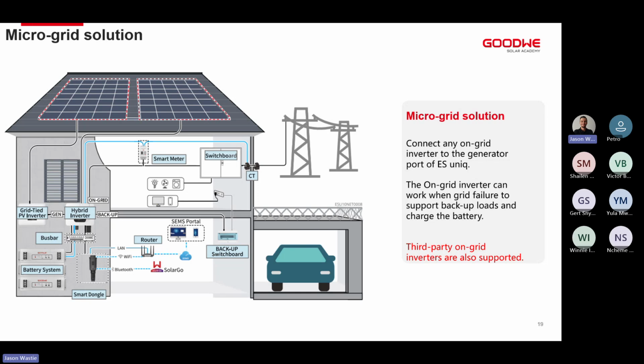One caveat to that, we just need to note that the grid-tied inverter can only be of the same power capacity as a hybrid inverter or smaller. So if we have a 10 kilowatt hybrid inverter, we can only use as much as a 10 kilowatt grid-tied inverter, no more, and obviously smaller is fine.